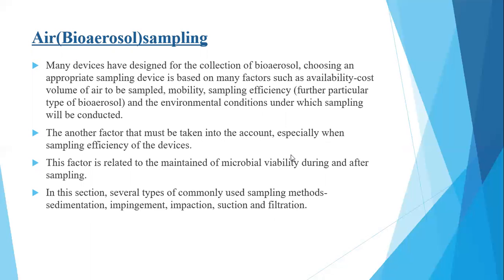The next topic is bioaerosol sampling. Many devices have been designed for the collection of bioaerosols. Choosing an appropriate sampling device is based on many factors such as availability, cost, volume of air to be sampled, mobility, sampling efficiency, and the environmental conditions under which sampling can be conducted. Another factor must be taken into account, especially regarding sampling efficiency: the maintenance of microbial viability during and after sampling.